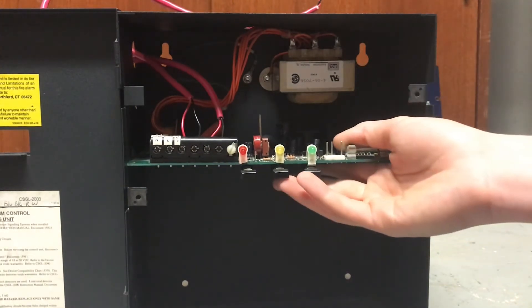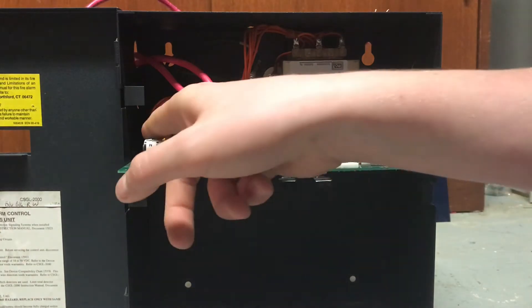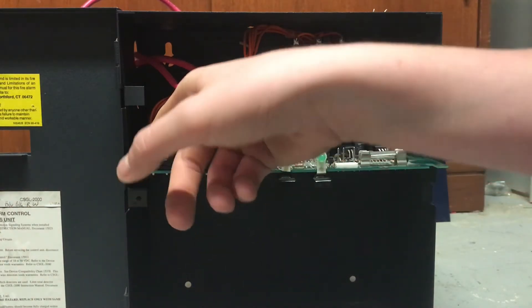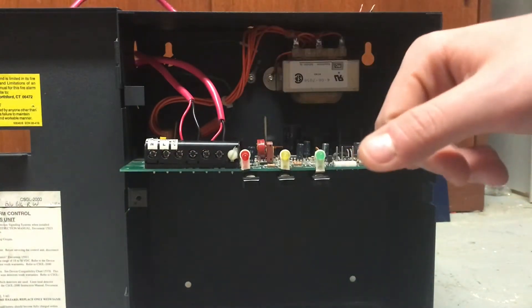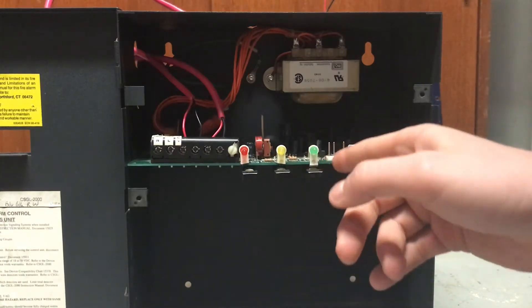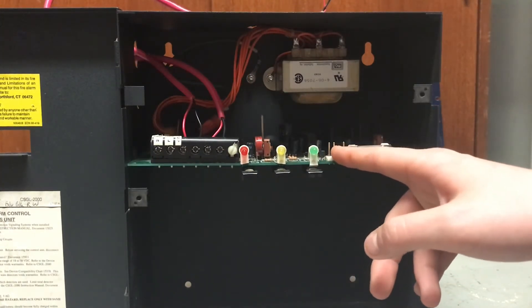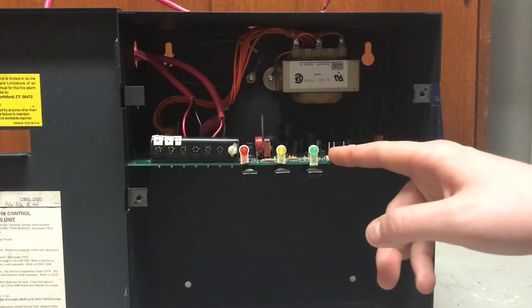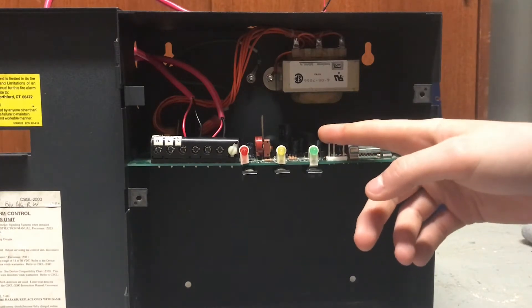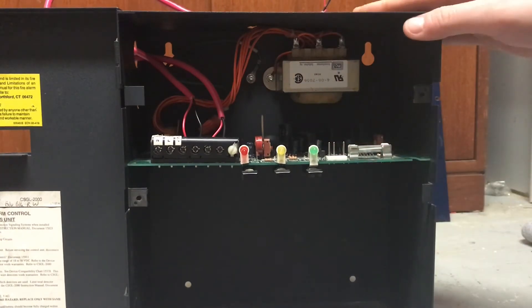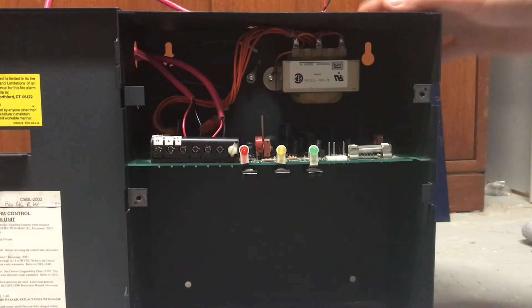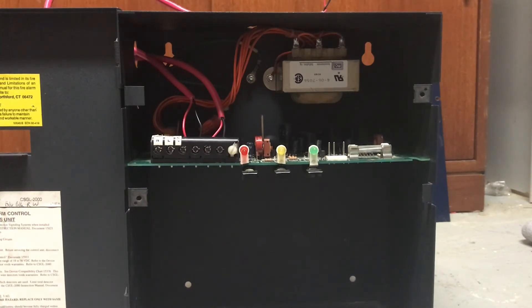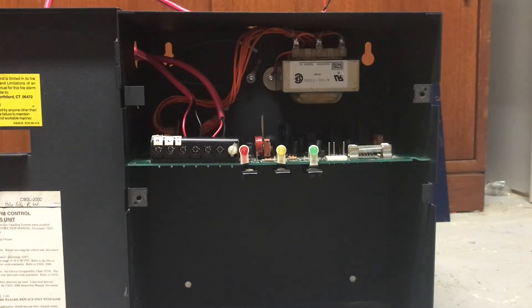Basically, yes, this panel is very, very simple, and it's got some other stuff. It's got a capacitor, you got your piezo, you got a fuse for the NACs, and you have your battery pins, which a harness would go on, but I'm actually using the harness for the NFW-50's batteries. So this thing basically just has a battery trouble. Another thing I should mention, these panels take, I believe, 4.7K ohm resistors. So now that you know what it looks like on the inside, we will go ahead and power this thing up, and I will give you a demonstration of how it works.